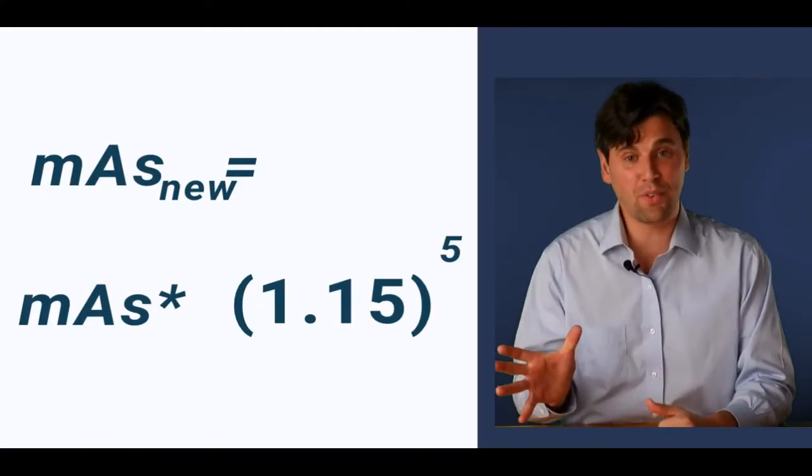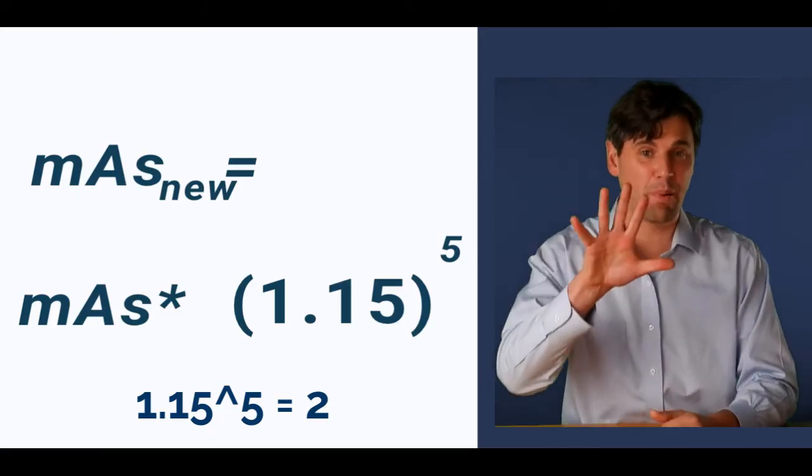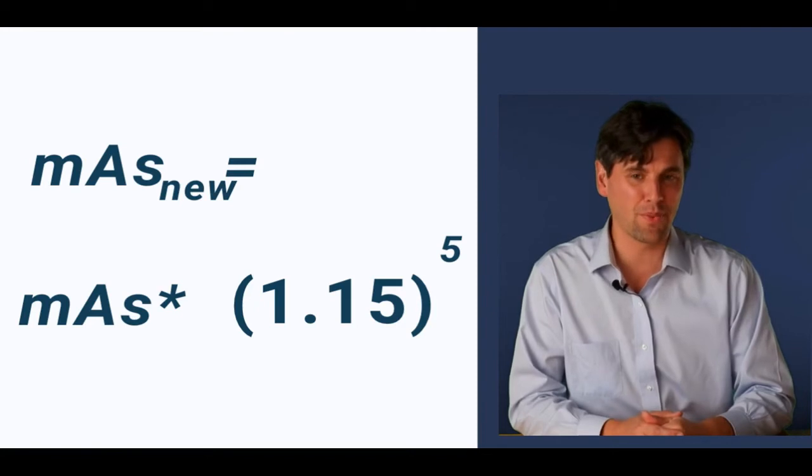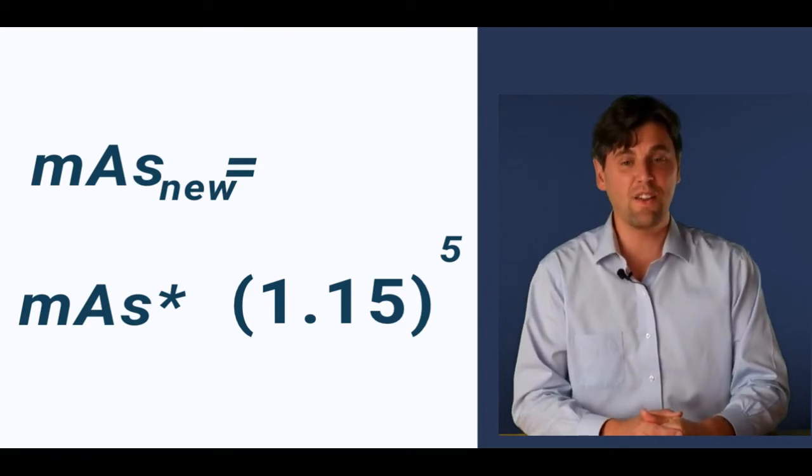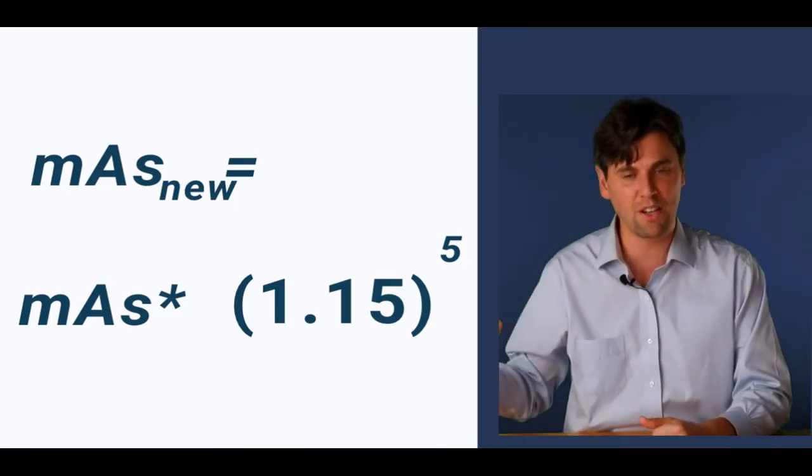1.15 is a 15% change. And if you think about 1.15 raised to the fifth power is actually 2. That's where your 15% rule comes from. The fact that KVP is very strongly an influence on both the x-ray generation and the x-rays that actually penetrate the patient. It's as simple as that.